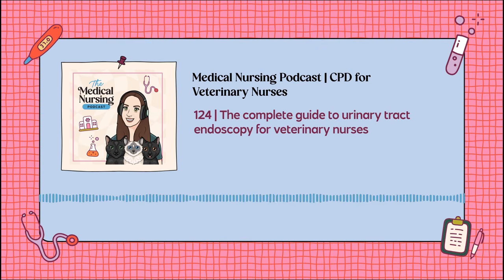The scopes will be connected to the endoscopy tower, the camera, the light cable, of course, as needed, as our other scopes would be. Now, most of our flexible urethra cystoscopes will plug directly into the tower without needing an external camera or a light source because they are usually video endoscopes. Rigid telescopes, on the other hand, will need to be attached to a camera head and a light cable, and this should also be sterile or cold soaked or covered with a sterile camera drape if you have access to those.